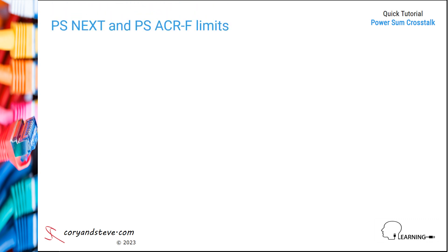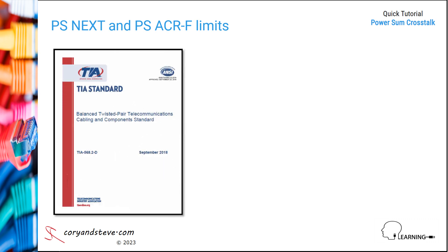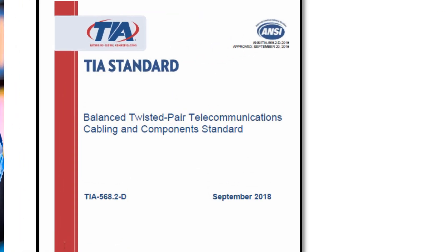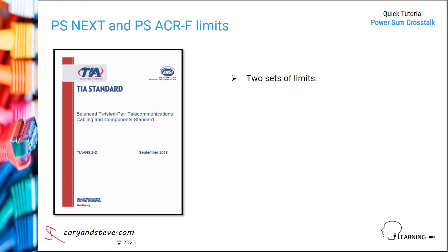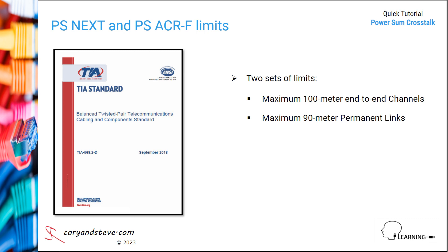We'll finish this module with a review of the published PS-NEXT and PS-ACRF limits for categories 5E, 6, 6A, and 8. The applicable standard is the Telecommunications Industry Association or TIA 568.2-D, titled Balanced Twisted Pair Telecommunications Cabling and Components Standard. There are two sets of limits: one for maximum 100 meter end-to-end channels and the other for maximum 90 meter permanent links. The channel limits are lower because of the cords added at both ends.